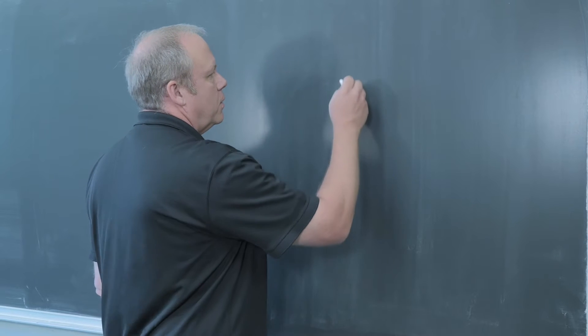It's known as a Penning ion gauge. It relies on the fact that we immerse the ion source in a uniform magnetic field, which is easy in the cyclotron. We put this right in the center of our machine. There's a tube which we call the chimney. The tube is grounded. We inlet some hydrogen gas. Pressure inside here is probably on the order of tens of millitorr.